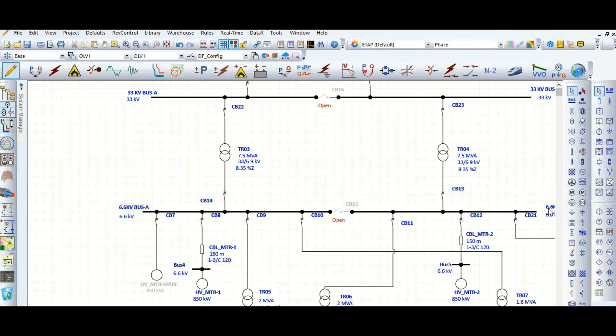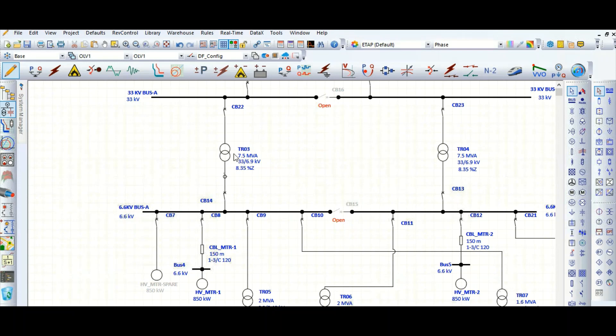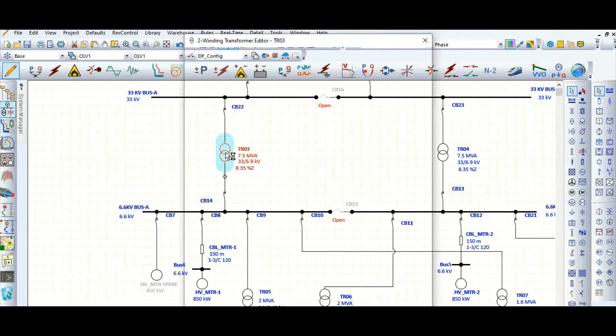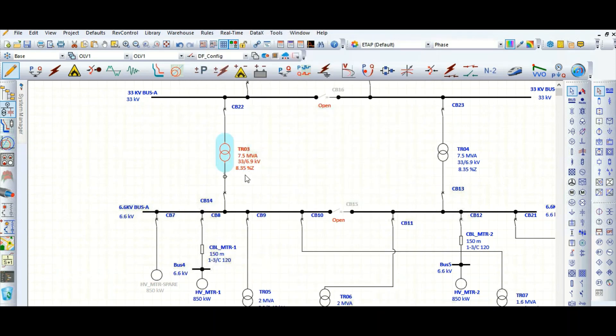I will explain briefly how to do that. So for the relay, before using the relay we need to specify the current transformer. So this is the CT. What will be the CT ratio? Let's check here the transformer secondary continuous current rating. Here primary secondary side, 6.6 kV side, this is 627.6 amps full load current. So let's select this CT ratio.